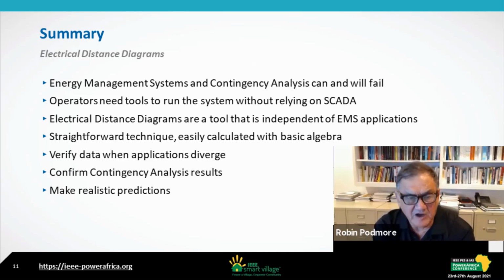And as we're obviously more and more systems are putting in energy management systems with contingency analysis. But again, it's not just a matter of if they're going to fail, it's just a matter of when, because a data error can cause a failure, a communications link can cause a failure, and also obviously a cyber attack can cause those applications to not be available. And so when we have this whole environment where we're so dependent upon applications and data can actually cause those applications to diverge, or even when everything is running perfectly well and your contingency analysis is predicting, say, a voltage collapse, it's really good to have other tools where you can independently make the calculations to verify that your applications are really giving you something that is a very realistic prediction of what could happen in the future.